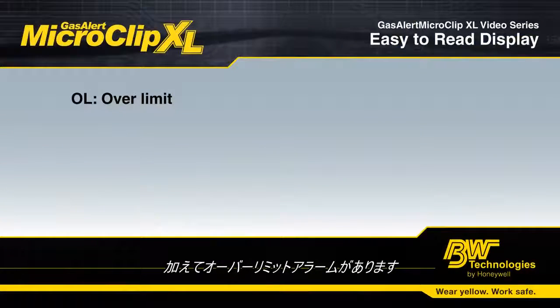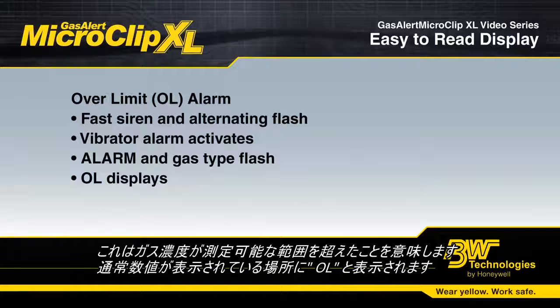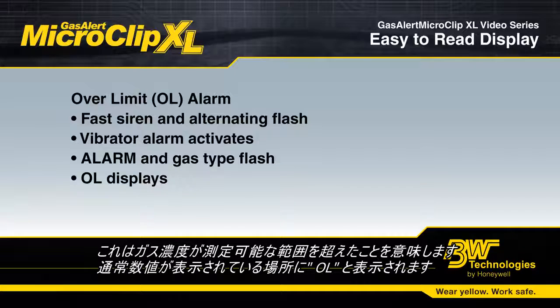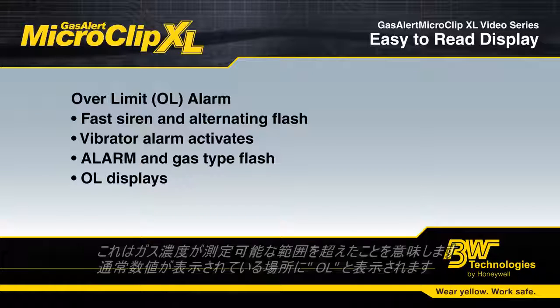The fifth type of alarm is an OL, or Over Limit Alarm. This means that the level of gas in the environment is beyond what the sensor can measure. OL will flash in place of the reading of that sensor.